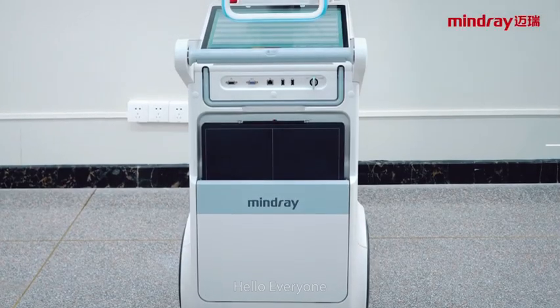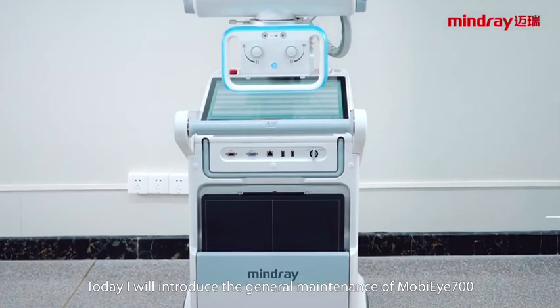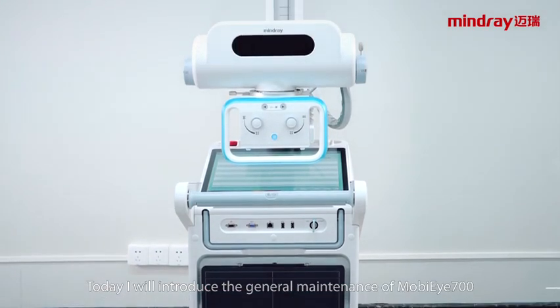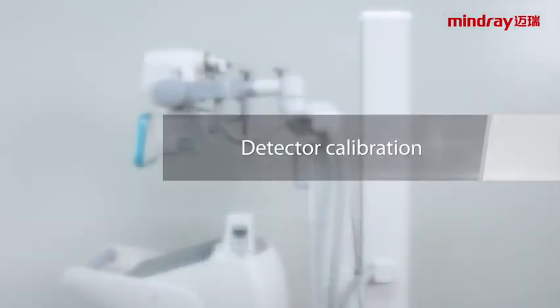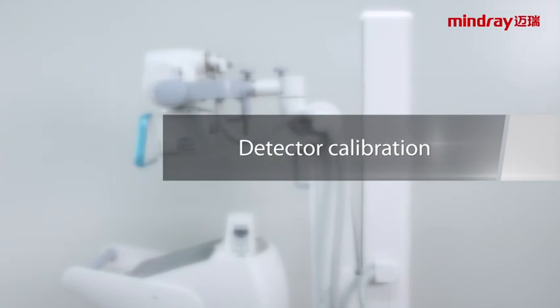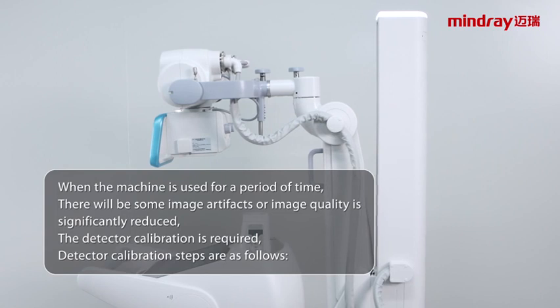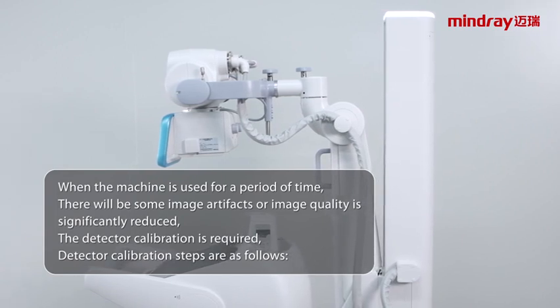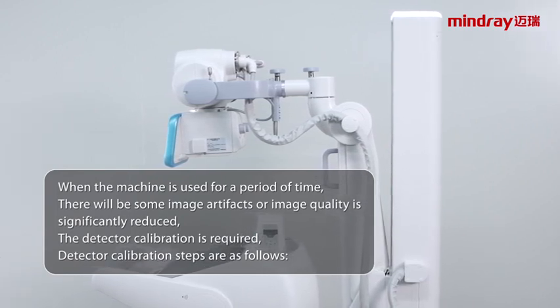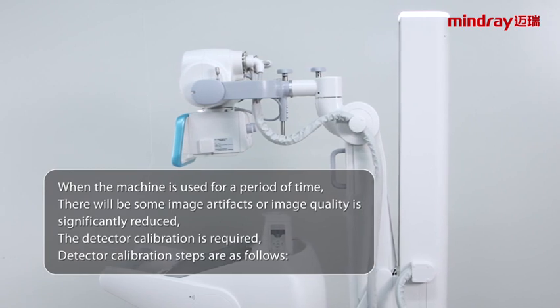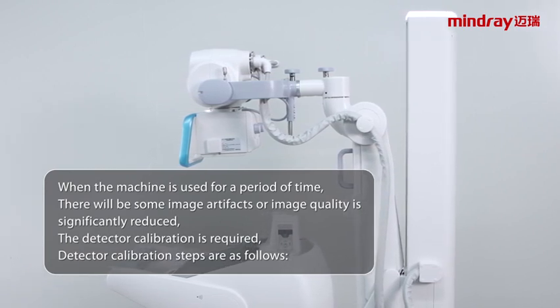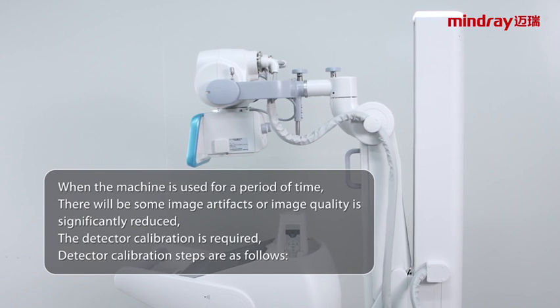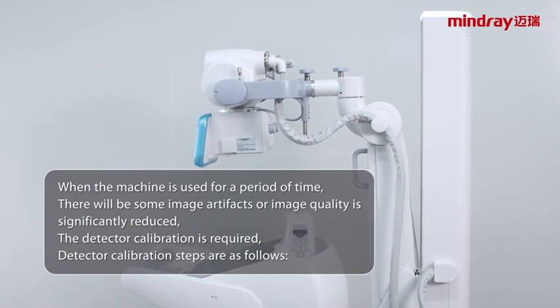Hello everyone, today I will introduce the general maintenance of MobiEye 700. Detector calibration. When the machine is used for a period of time, there will be some image artifacts or image quality is significantly reduced. The detector calibration is required. Detector calibration steps are as follows.